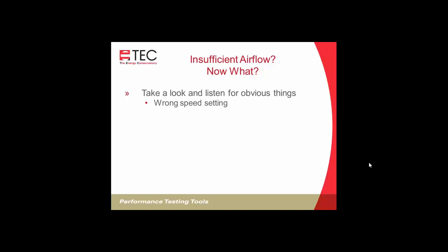Wrong speed settings on the fan, certainly increasing those fan speeds will help. Whenever you do that, you want to check static pressure, and we'll be going over that a little bit later. But try upping the fan speed to get more airflow, and that may be a solution as long as your static pressures aren't getting too high, because that's going to be hard on the longevity of your motor if your static pressures are too high.